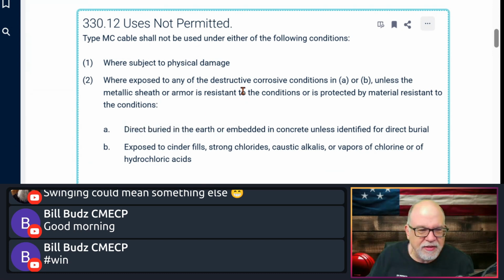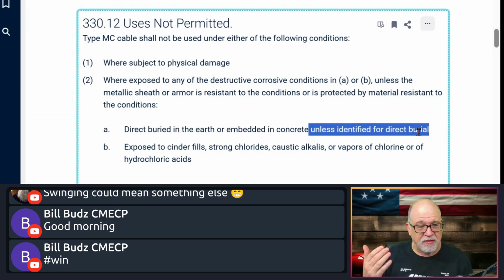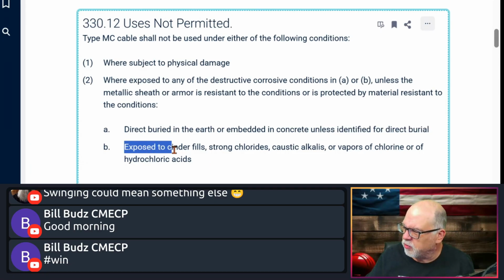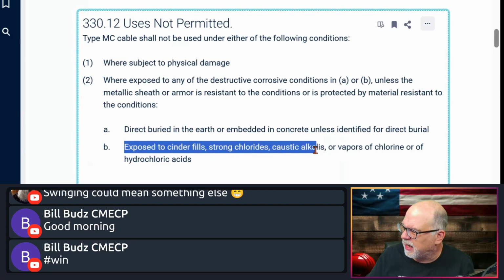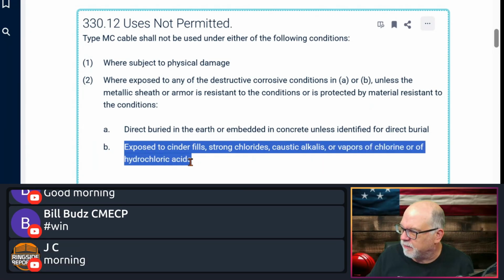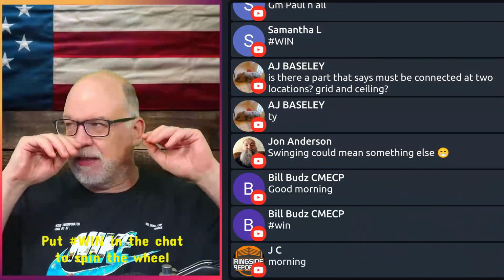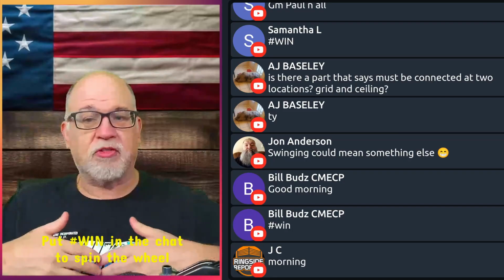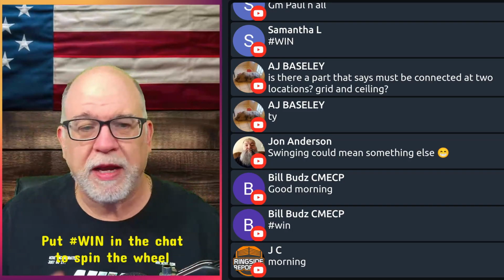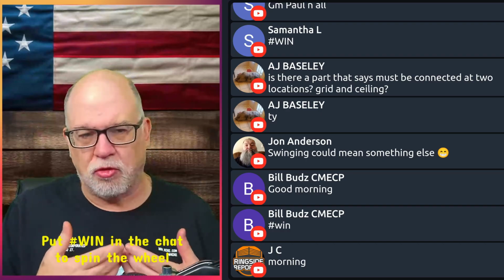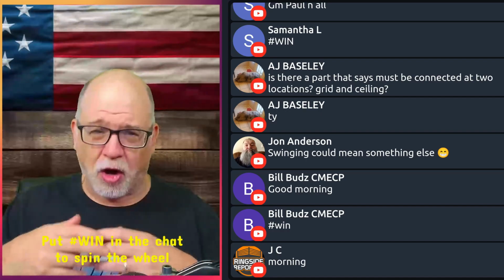Okay, so again, it can be direct buried in the earth. Use is not permitted unless it meets these conditions: direct buried in earth or embedded in concrete unless identified for direct burial. That would be an example of a PVC jacketed MC that's going to have the markings on it. Next, exposed to cinder fills, strong chlorides, caustic alkalis, or vapors of chlorine, like in a pool room, or of hydrochloric acid. PVC jacketing is very resistant to that. In fact, at Encore Wire, I did a study for 18 months back when we were trying to get the code, and explained the importance of this. It was something I really got immersed in a couple cycles ago, to educate people about the resilience of a PVC extrusion and the fact that we have conductors inside of it that are wet rated location.